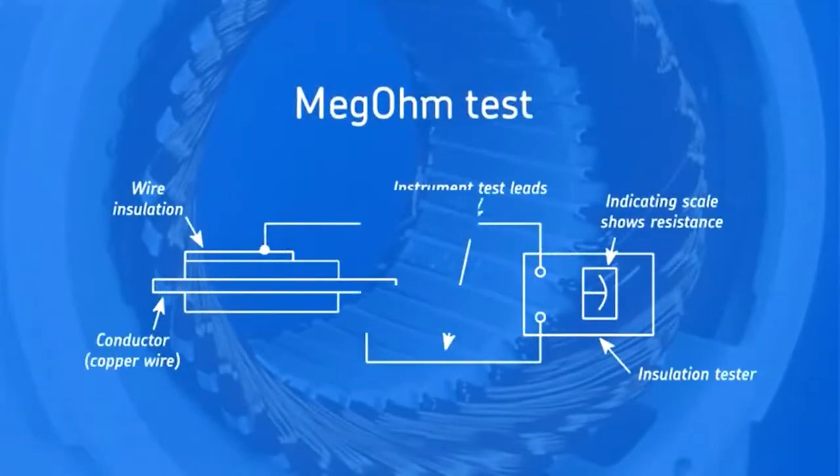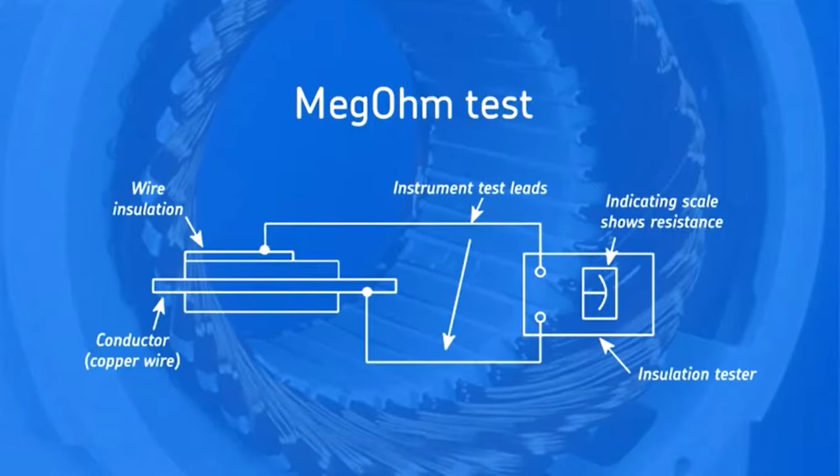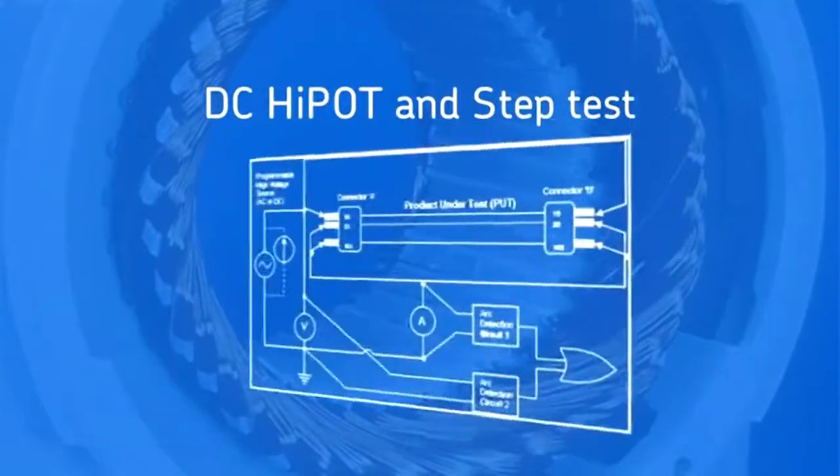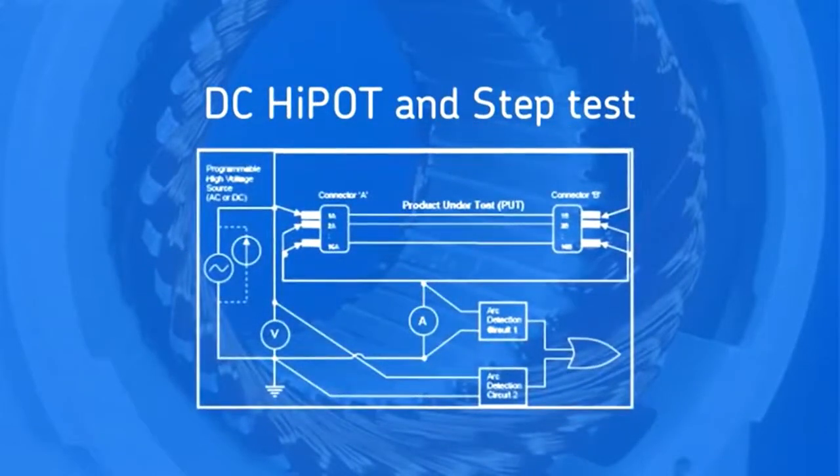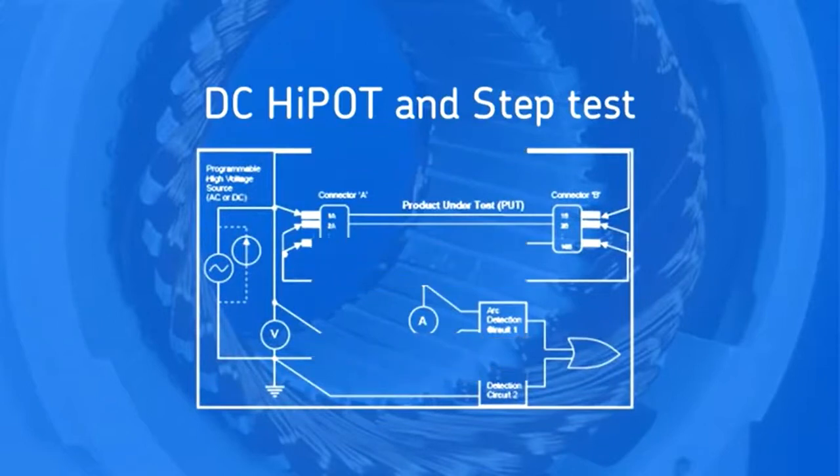Ground-wall insulation strength is measured with the meg-ohm test at low voltage, but this test misses many ground-wall insulation failures. A better test is the DC high-pot and step tests, which measure insulation strength at higher voltages. Stator insulation faults are responsible for about 30-40% of motor failures.